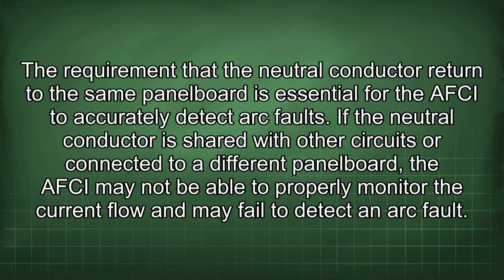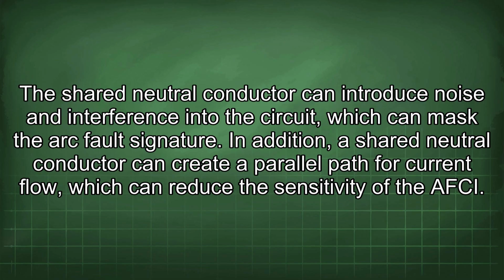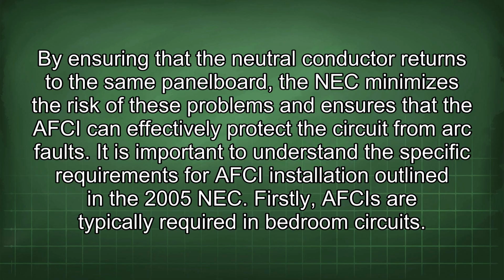detect arc faults. If the neutral conductor is shared with other circuits or connected to a different panel board, the AFCI may not be able to properly monitor the current flow and may fail to detect an arc fault. The shared neutral conductor can introduce noise and interference into the circuit, which can mask the arc fault signature. In addition, a shared neutral conductor can create a parallel path for current flow, which can reduce the sensitivity of the AFCI. By ensuring that the neutral conductor returns to the same panel board, the NEC minimizes the risk of these problems and ensures that the AFCI can effectively protect the circuit from arc faults.